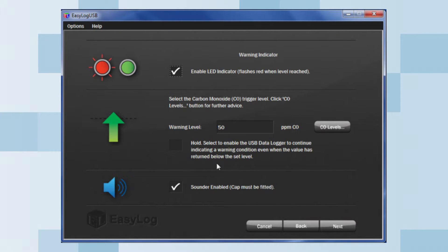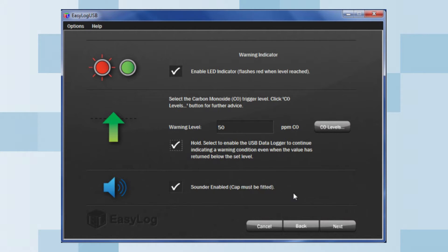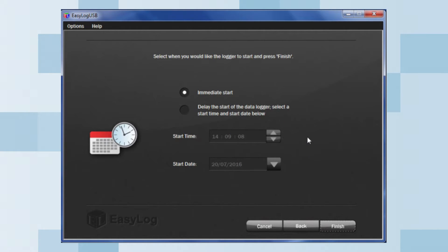Here is a hold option, which will enable the USB data logger to continue indicating a warning condition even when the value has returned below the set level. Next, you can enable the sounder. Note that for the sounder to work, the cap must be fitted. Once this is complete, click Next.